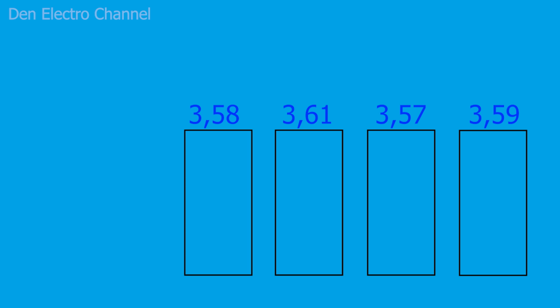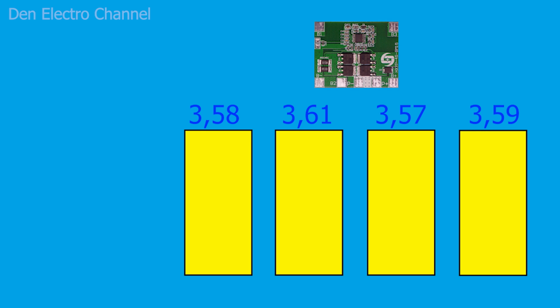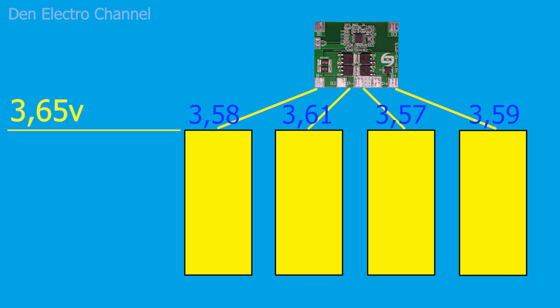In this state, we connect them to the BMS protection board. It will monitor the voltage of each battery. This protection board is one of the simplest, and therefore there is no voltage balancing function here. So even under its control, the batteries will always have different voltages. The maximum voltage will be limited to 3.65 volts, and the minimum to 2.35 volts.